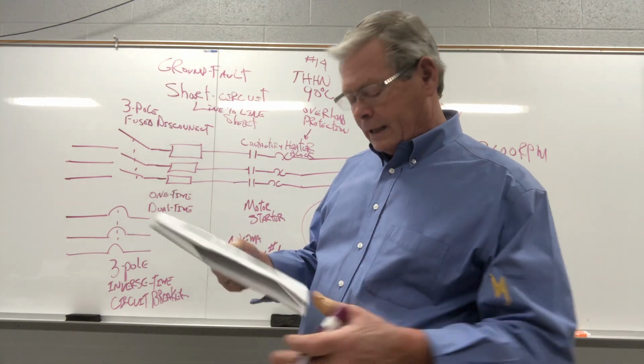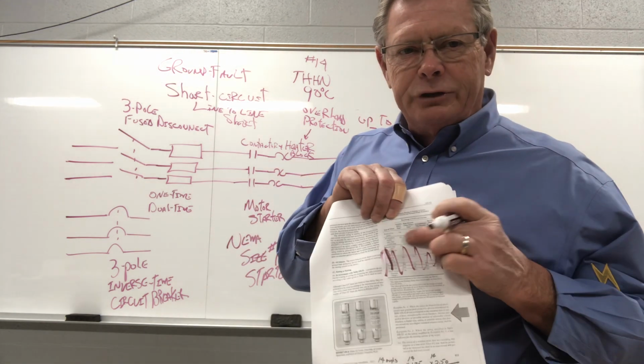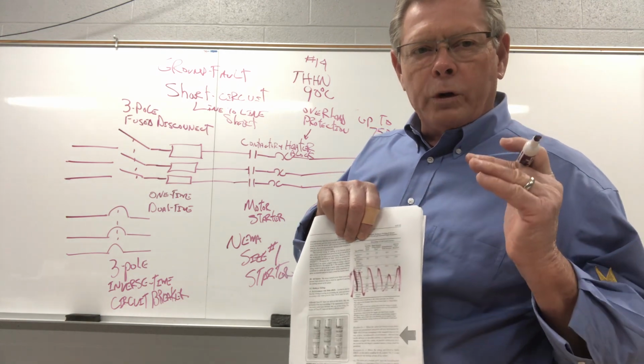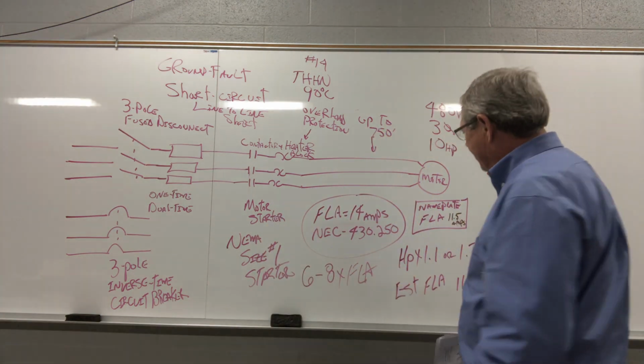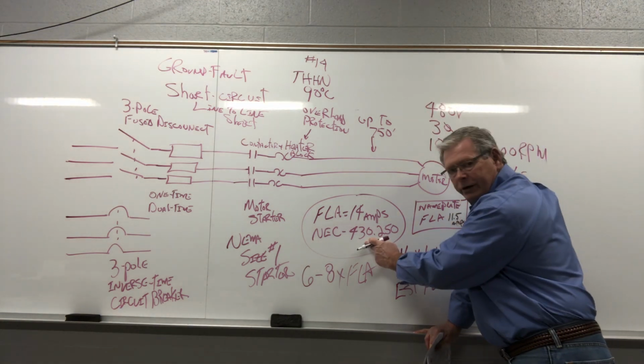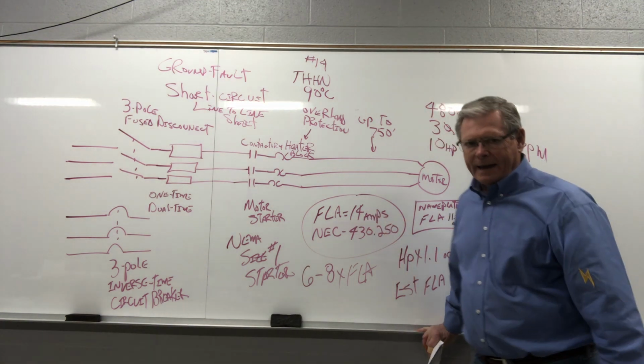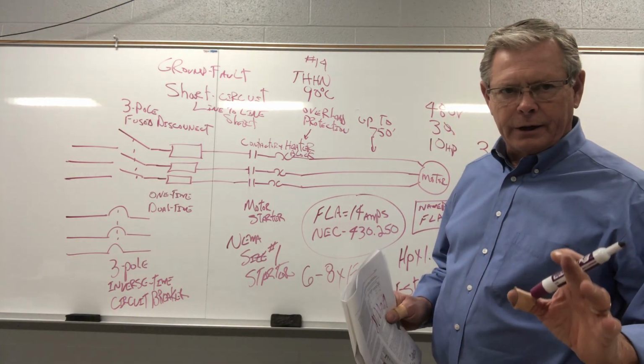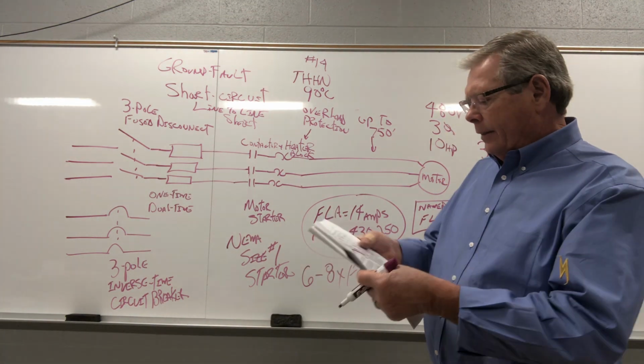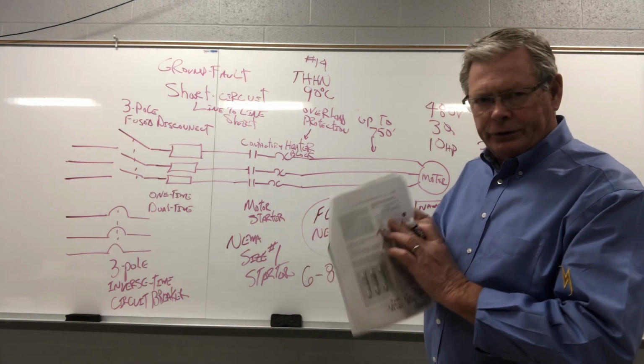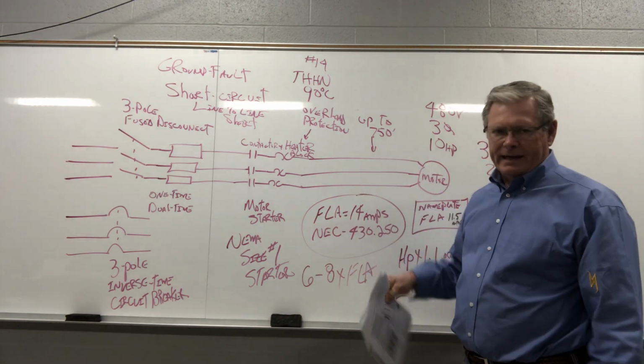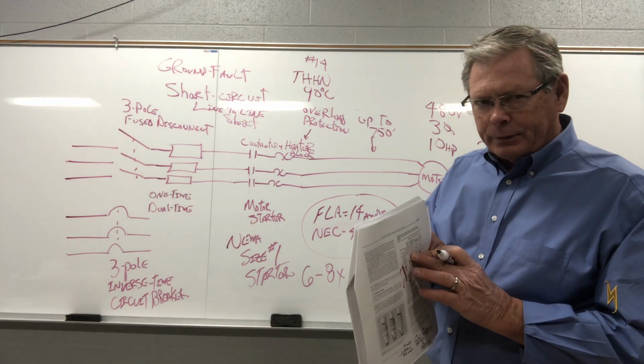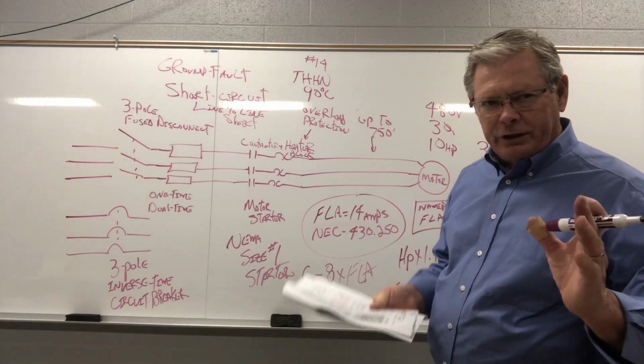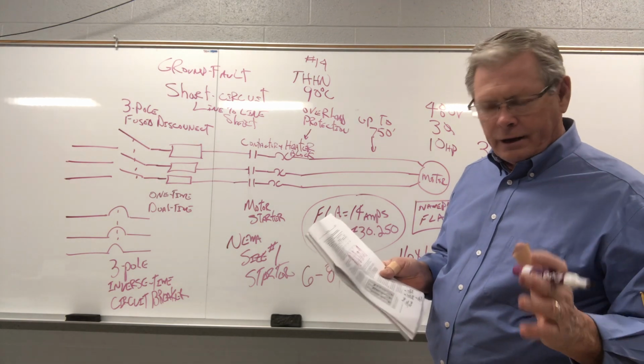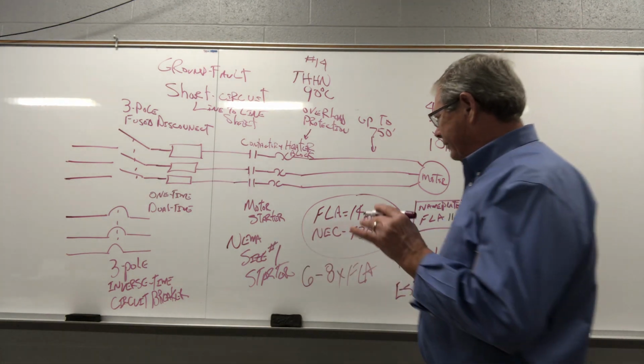First thing we're gonna do is a dual time fuse. If you look here, it gives you multipliers for your full load current. If we go back to 430.250, 14 amps is our worst case full load current for run current. This here says for a dual element fuse, if we multiply 14 amps times 175%, that's going to give us the figure we need for our dual element fuse. So that comes out to 24.5 amps.